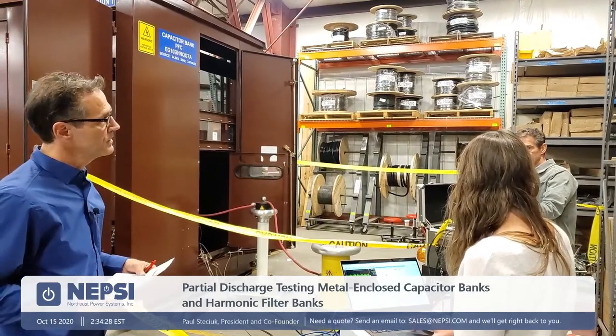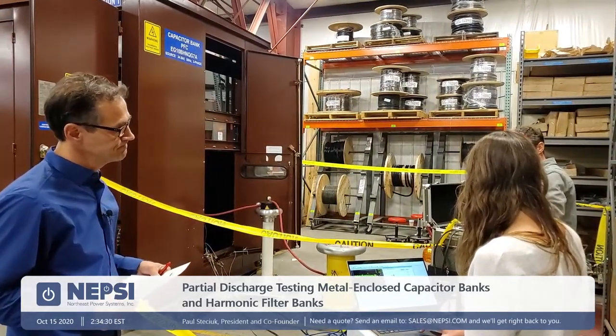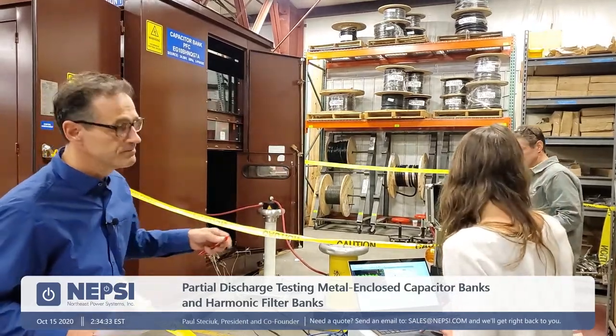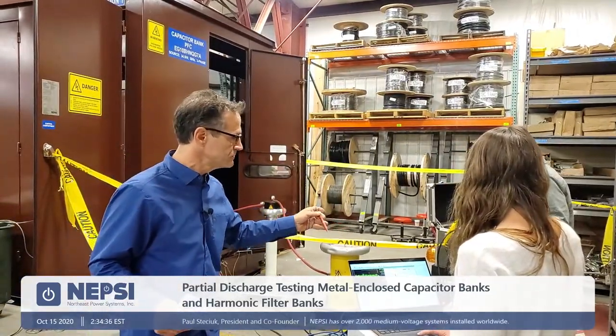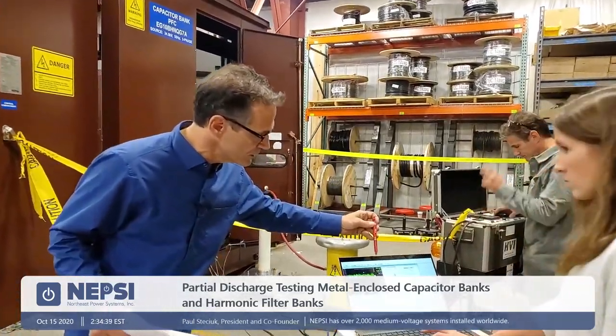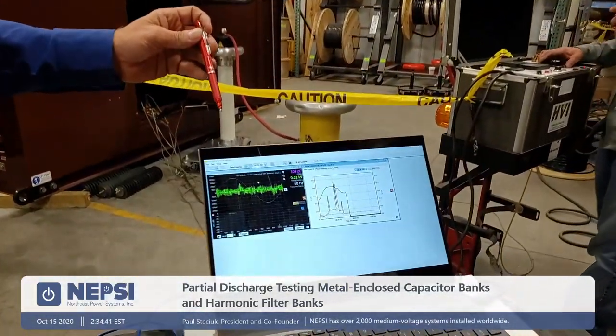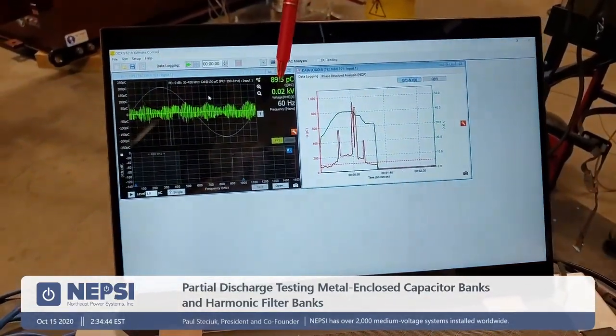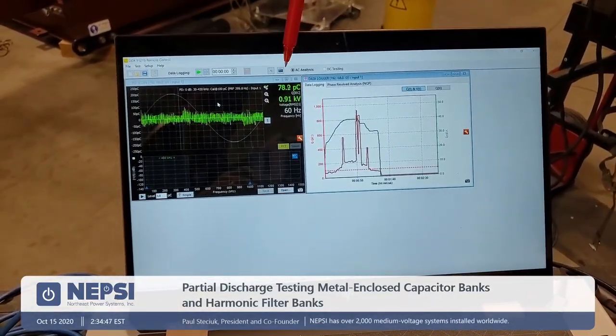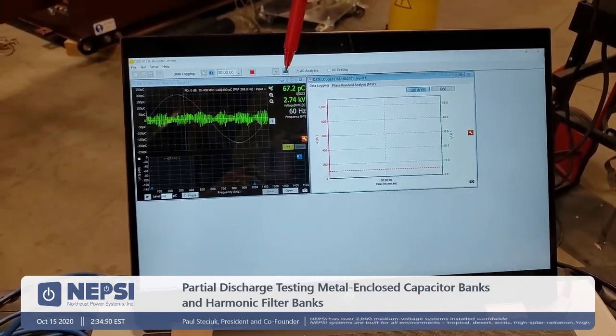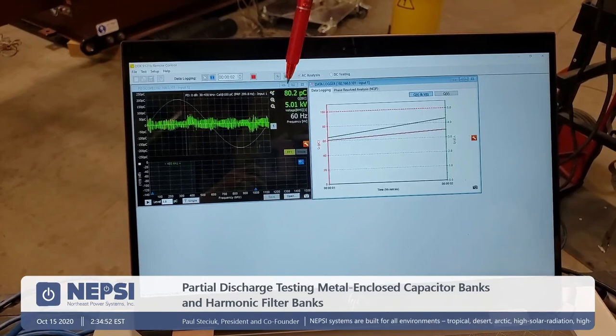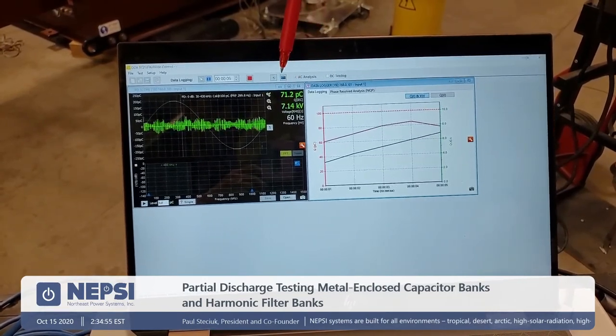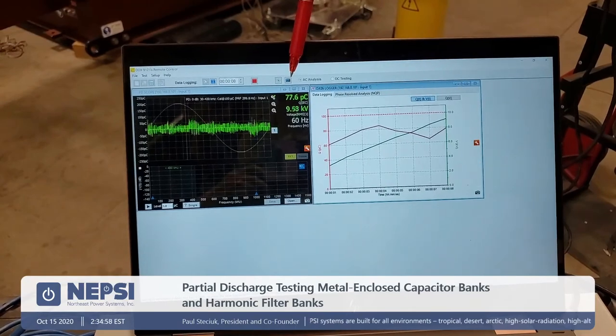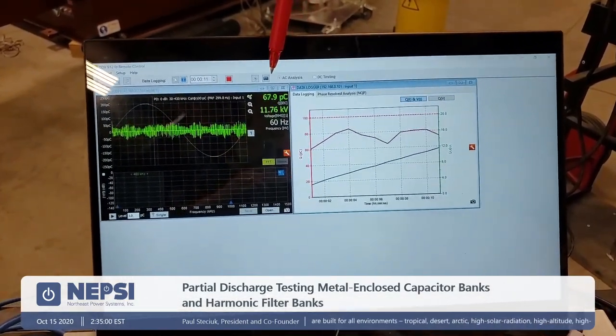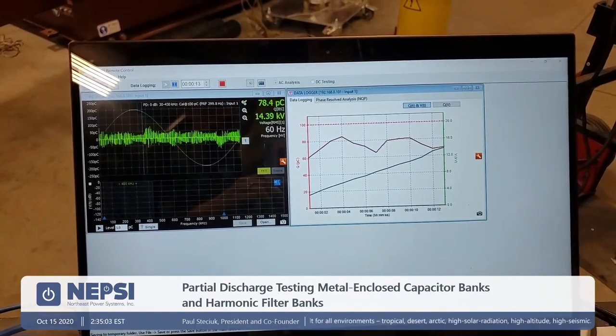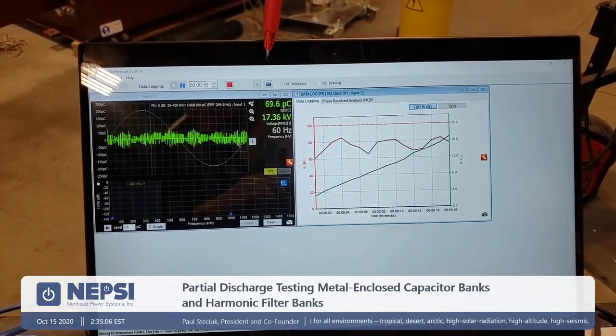So I'll bring the voltage up slowly, and so maybe you can see the partial discharge increase over the increased voltage. While you get Matt, why don't you come over here and get close up to the screen so the viewers can watch what's going on. So we're sitting at 0 kV right now. He's going to start raising the voltage. There you go. And you can see as we raise the voltage, the partial discharge will start to pick up. And this is picocoulombs. So we're at about 7 kV, and the picocoulombs is rising up through 80 picocoulombs here. As we continue to rise, you can see that the picocoulombs continues to rise.